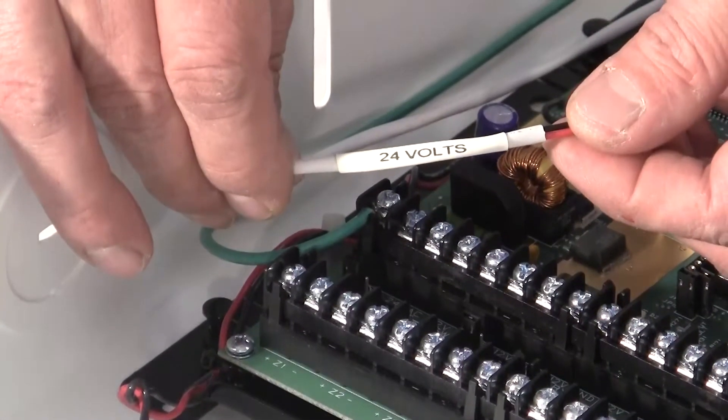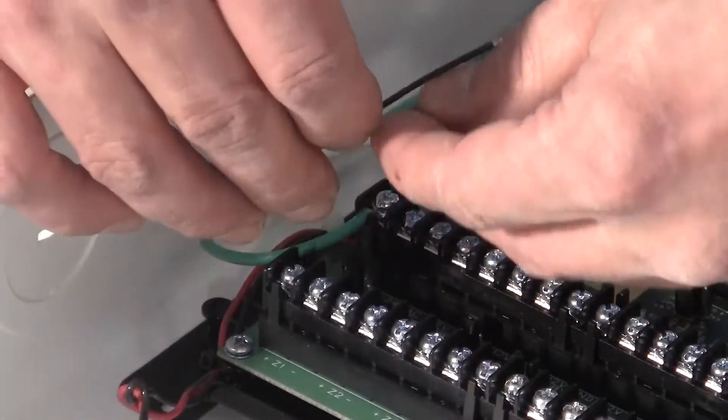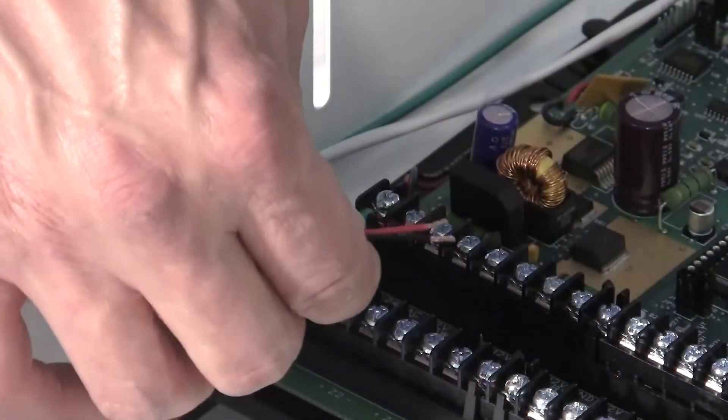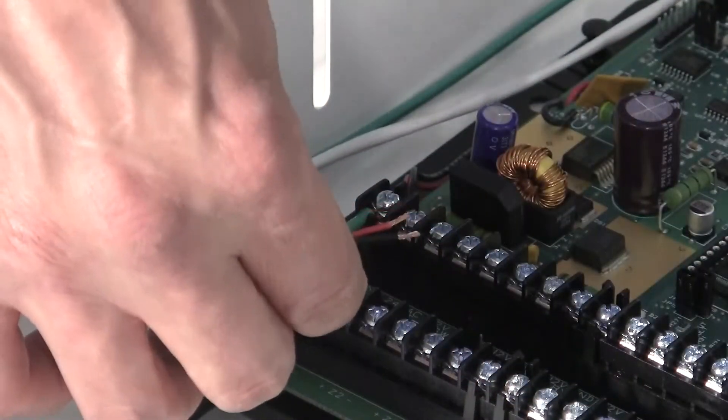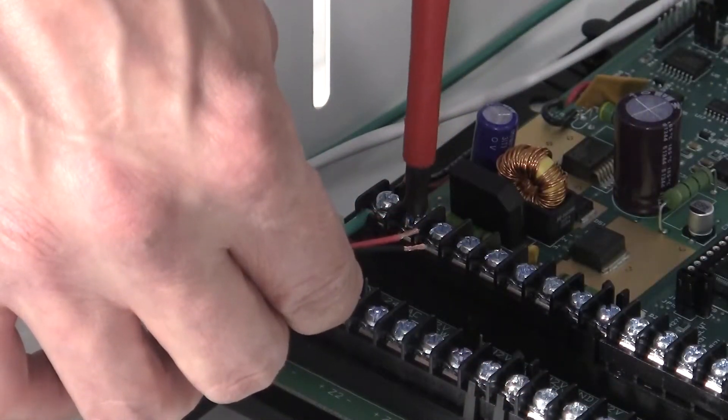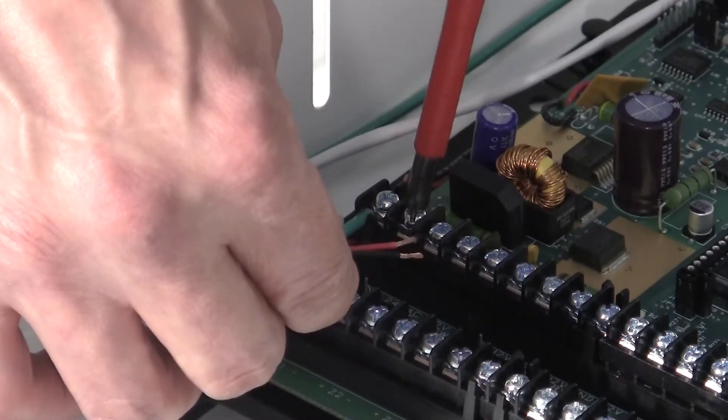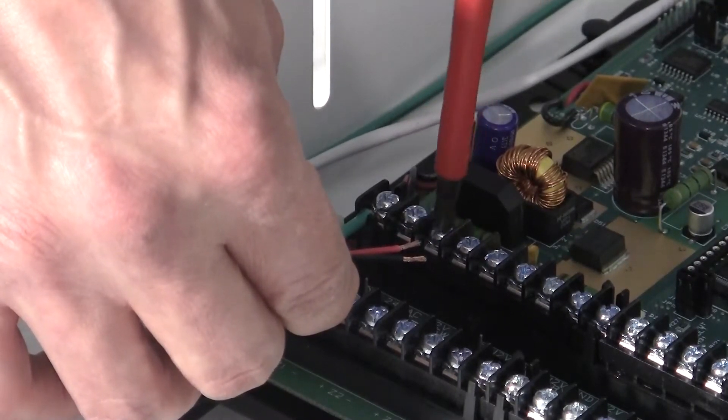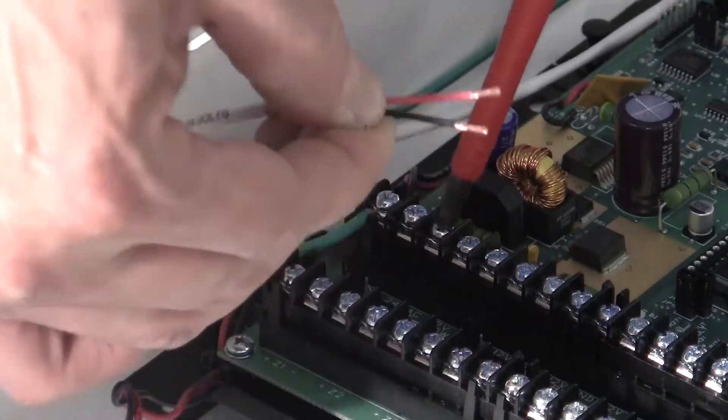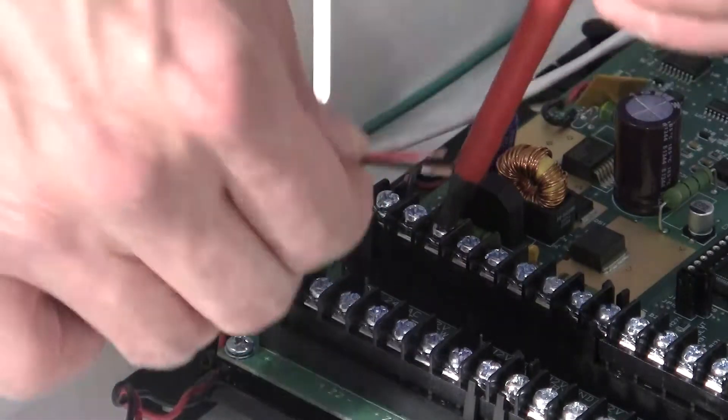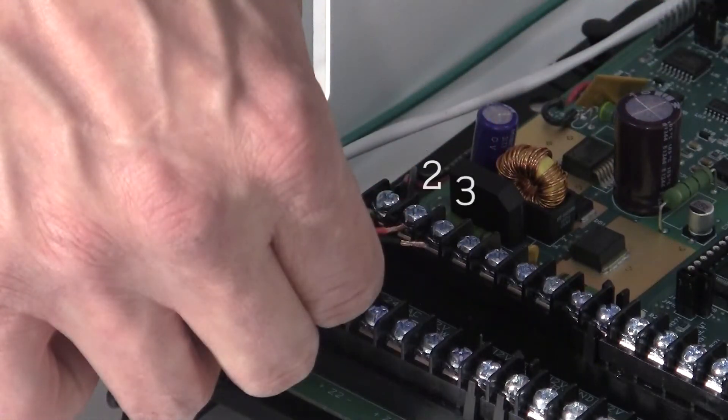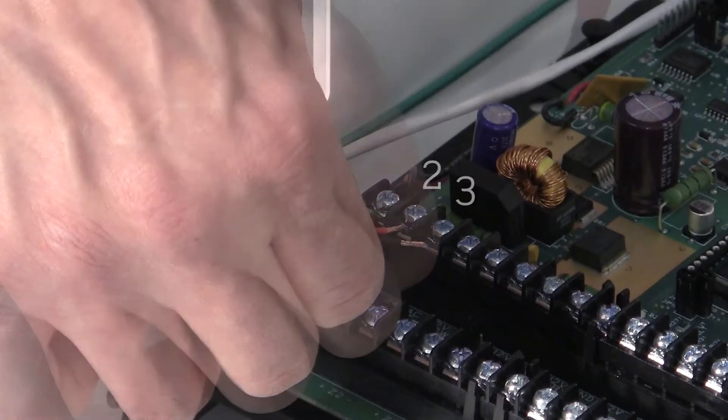Using 18-2 wire, connect a 24VAC 40VA transformer to the 24VAC input terminals, the second and third terminal inputs in the left corner of the first terminal strip. Be sure you have connected the wires to inputs 2 and 3 and not the first input, which should have been connected to the ground.